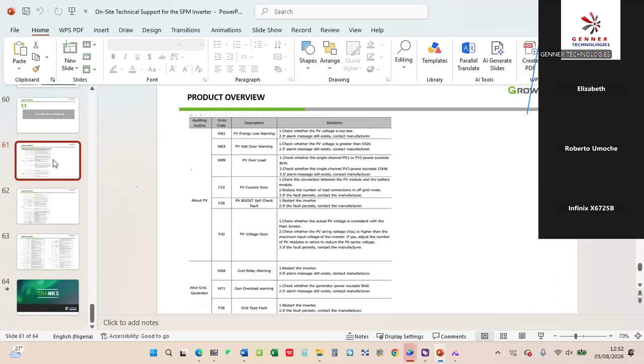So the errors here, you can see error 33, which is PV current over. When your current size is above the manufacturer's specification, the inverter brings this out, so it's necessary to stay within the voltage and range specified by the manufacturer. Going beyond it, the PV can still charge your battery, but going too far above, the current can damage the battery. So when you see F33, that's error 33, a PV current over.